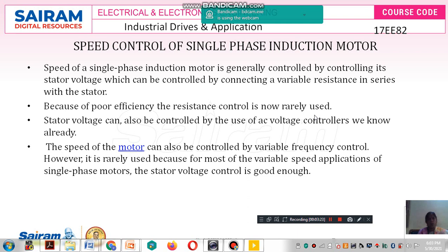The resistance-in-series method is very rarely used due to poor efficiency. The stator voltage can also be controlled by use of an AC voltage controller, which we discussed in the previous session. If the available source is AC, we use an AC voltage controller; if the available source is DC, we use a DC chopper — to convert fixed voltage to variable voltage in order to control the speed of the induction motor.